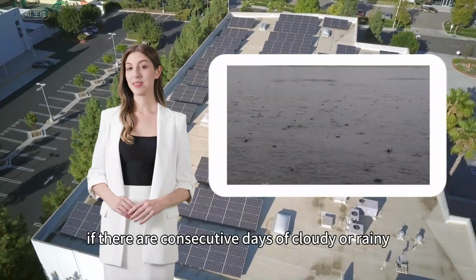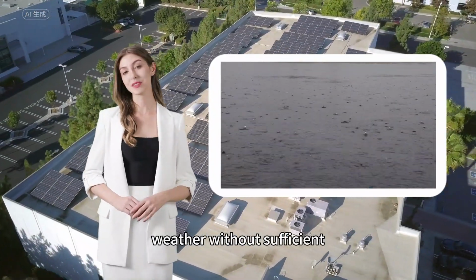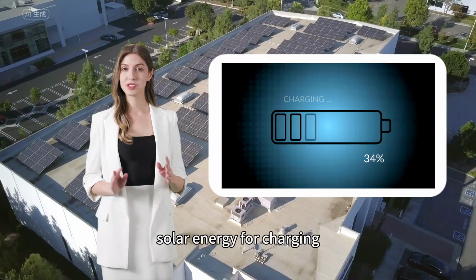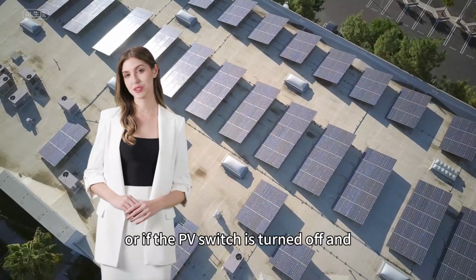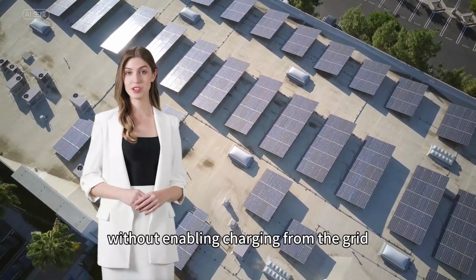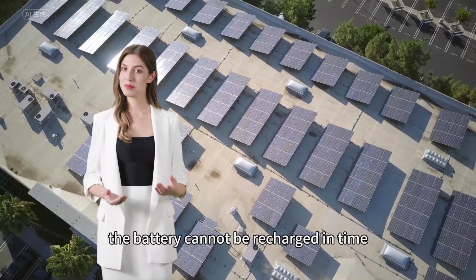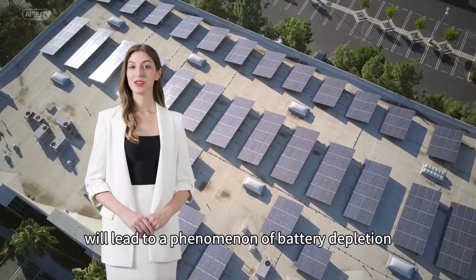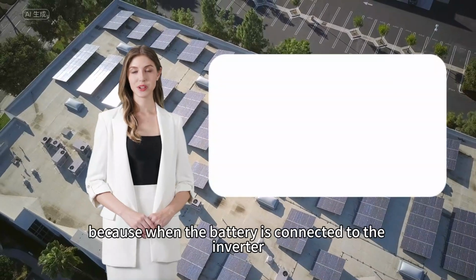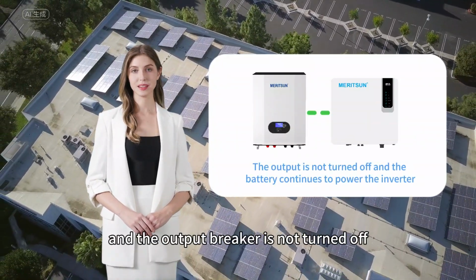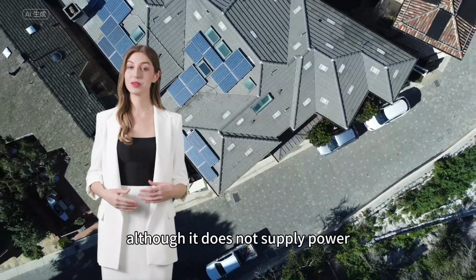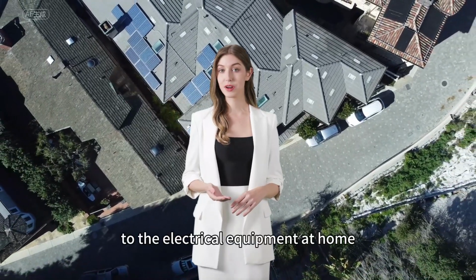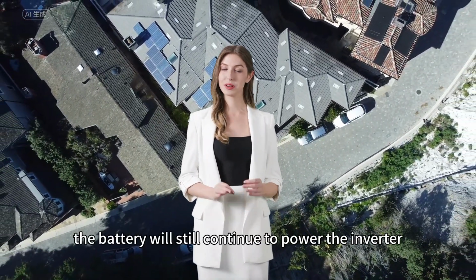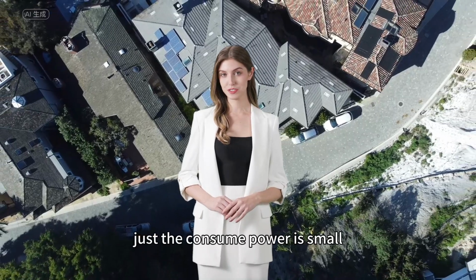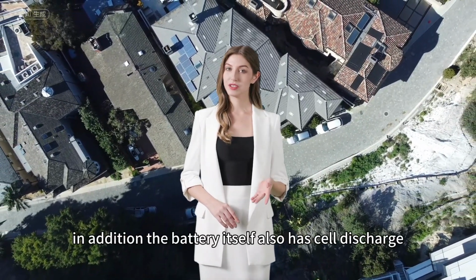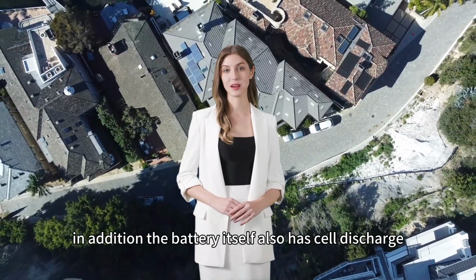However, if there are consecutive days of cloudy or rainy weather without sufficient solar energy for charging, or if the PV switch is turned off and charging from the grid is not enabled, the battery cannot be recharged in time and will become depleted. This is because when the battery is connected to the inverter and the output breaker is not turned off, although it does not supply power to the electrical equipment at home, the battery will still continue to power the inverter, just with small power consumption. In addition, the battery itself also has cell discharge.